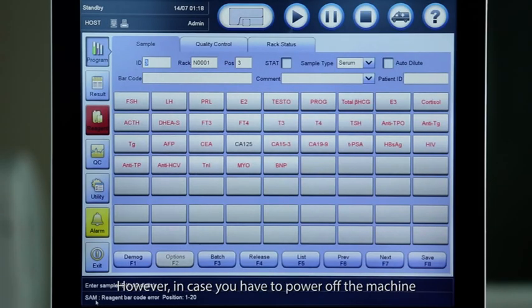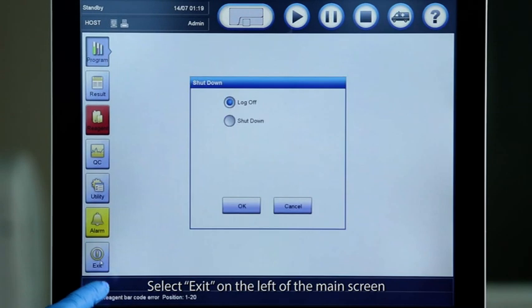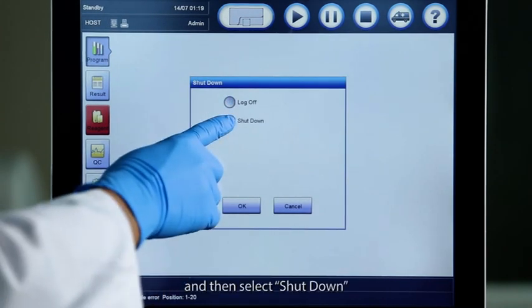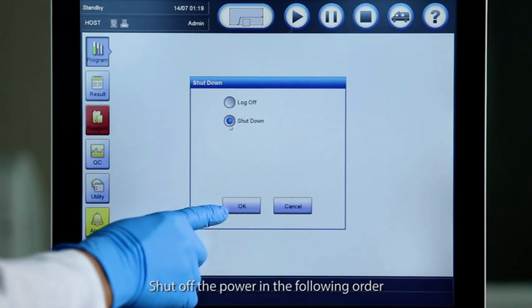However, in case you have to power off the machine, please make sure that the system is in standby status. Select exit on the left of the main screen and then select shut down. Shut off the power in the following order: Printer, monitor, and analyzer power switch.